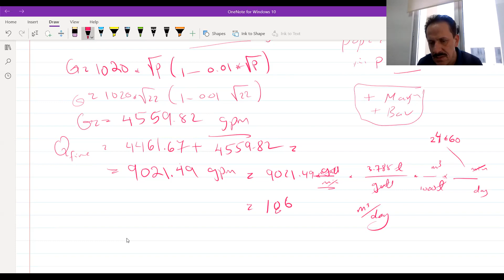186.11. Now remember this number: 186.1 meter cube needed for a full-day fire. But in reality, we don't, because the day in this fire is not 24 hours. When we are adding this fire to the normal day, the fire day is 10 hours and the normal day is 24 hours, right? So we need to multiply this 186.1 by 10 over 24.